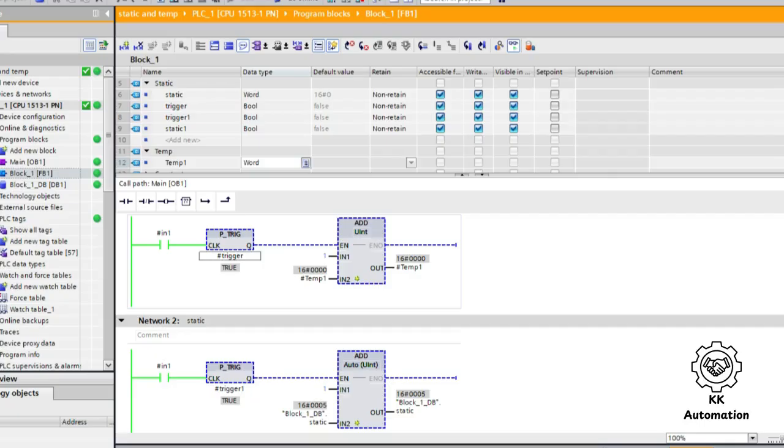Why this matters, the core difference. This concept of remembering data is the key. Temporary variables are fast and memory efficient. They use a shared pool of memory called the local data stack. A function grabs memory when it needs it and releases it as soon as it's done, allowing the next function to reuse that same memory. This is perfect for short-term calculations where you don't need to remember the result, like finding the average of two numbers. Static variables are persistent.